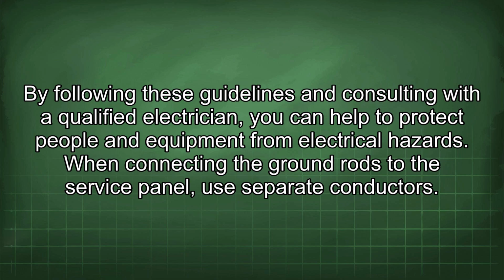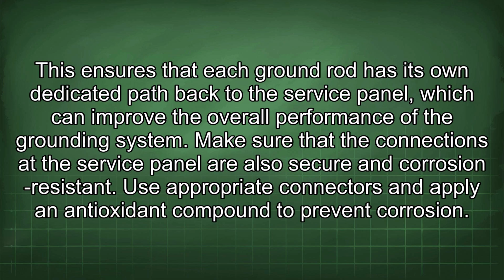hazards. When connecting the ground rods to the service panel, use separate conductors. This ensures that each ground rod has its own dedicated path back to the service panel, which can improve the overall performance of the grounding system. Make sure that the connections at the service panel are also secure and corrosion resistant. Use appropriate connectors and apply an antioxidant compound to prevent corrosion.